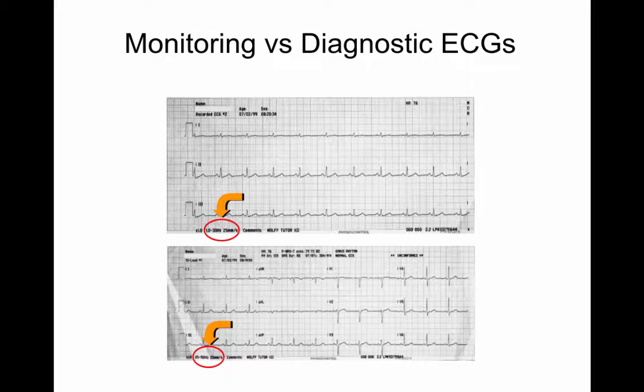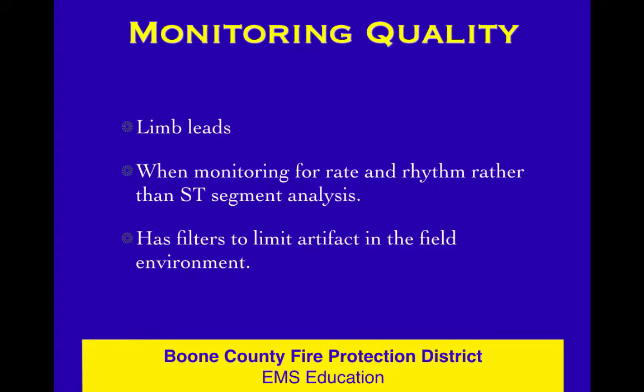Monitoring versus diagnostic EKGs: when you look at the same EKG on a person in monitoring quality and then again in diagnostic quality, different things will show up. Diagnostic quality is where you can determine ST elevation. Monitoring quality is great — it works in limb leads and gives you rate and rhythm. There's not going to be any difference in rate or rhythm on a diagnostic quality EKG from what you're seeing in monitoring quality. You just can't look at ST segment analysis unless you're in diagnostic quality. There's all kinds of interference in the field that causes artifact, so filters are in place to help you get a clean tracing for rate and rhythm — you just cannot use that for all pieces of analysis.